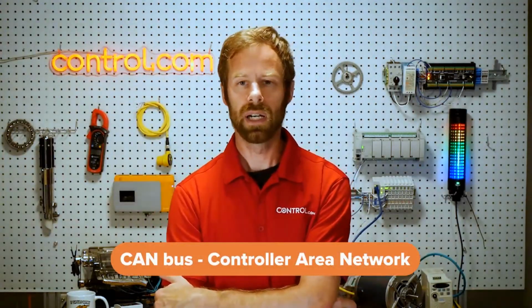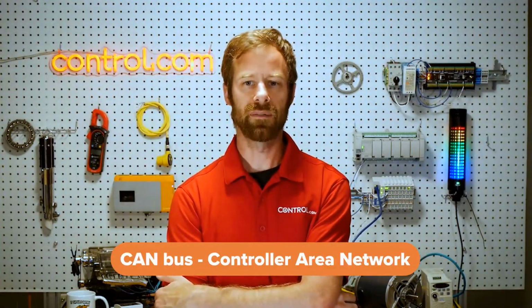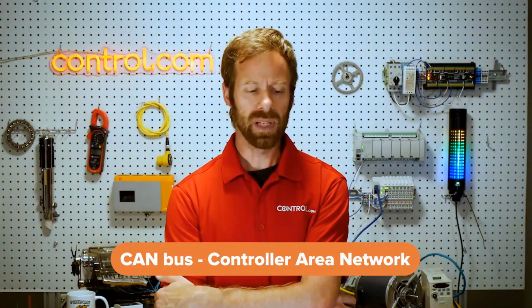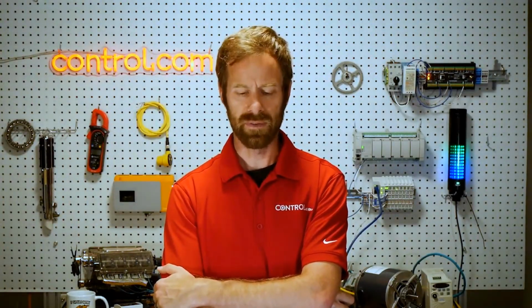Another one to talk about is called CAN bus, or Controller Area Network. This one was originally developed as a vehicle standard, and now we see a variation of that showing up in nearly all vehicles produced since the mid-90s, which is the OBD2 interface. All the sensors that are connected to the control module were connected with this Controller Area Network, or CAN. CAN can provide a lot of information at really high speeds. It usually uses a variation of RS-485, but it can exceed the speeds of a normal RS-485 connection, so that makes it great for some of the more complex systems.